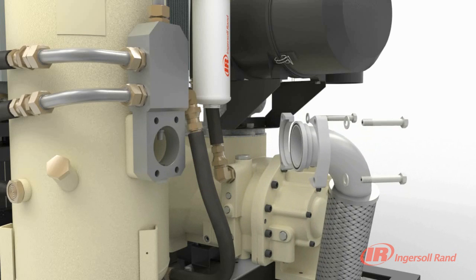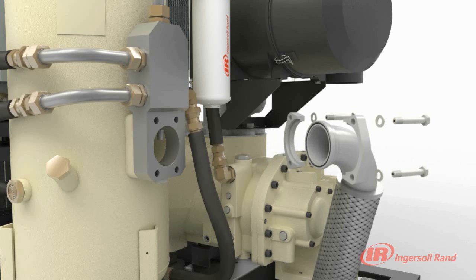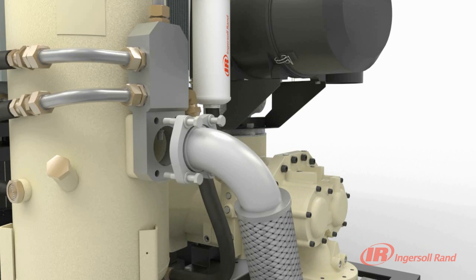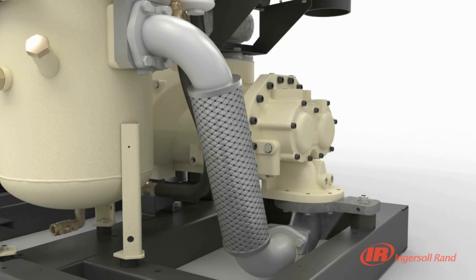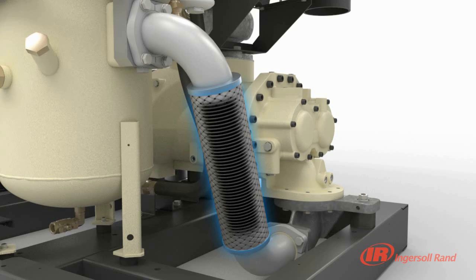This O-ring face seal design allows for practically unlimited reconnections. The V-Shield Technology also includes the use of premium metal flex hoses that significantly reduce vibration and noise while improving durability, thus ensuring long life of the compressor. The corrugated inner design isolates vibration and reduces noise, whereas the exceptional stainless steel outer braid provides abrasion resistance and protection against elongation.